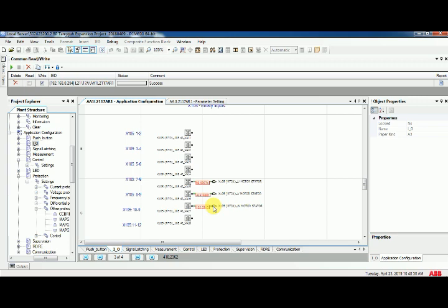Now I'm going to remove U-phase winding temperature 145 ohms and replace it with 99 ohms resistor. Now check online, you can see the temperature value changed.